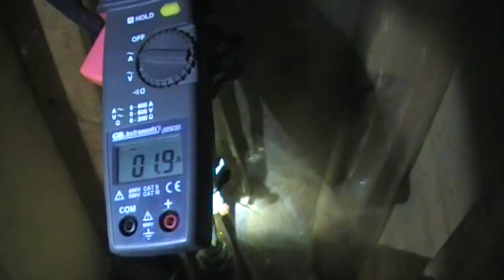We'll go back to the meter and you'll see we're still showing, actually just when I came over we jumped up to 4.8 but still kind of holding around 1.8, 1.9, so really no change. When I bring the magnetic field meter back, again it's pegged the meter well over 100. This problem is resulting from current coming from outside the house to get back to the transformer through our piping.